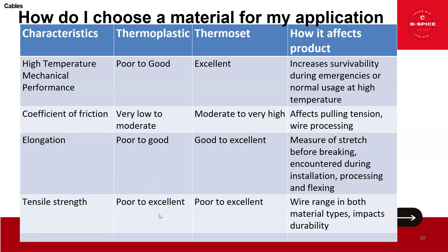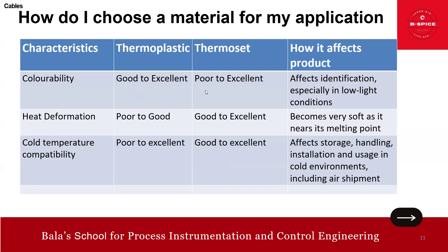Tensile strength shows a wide range in both material type and impact durability — not much difference between the two. But when it comes to high temperature, thermoset scores. Coefficient of friction — thermoset scores. Elongation — thermoset scores. Colorability: thermoplastic is good to excellent; thermoset is poor to excellent — it affects identification especially in low light conditions, which is a challenge for thermoset.